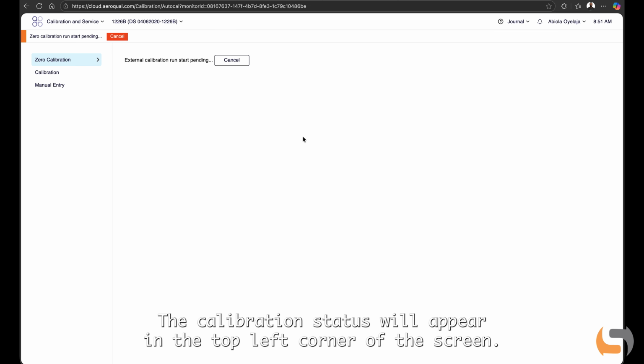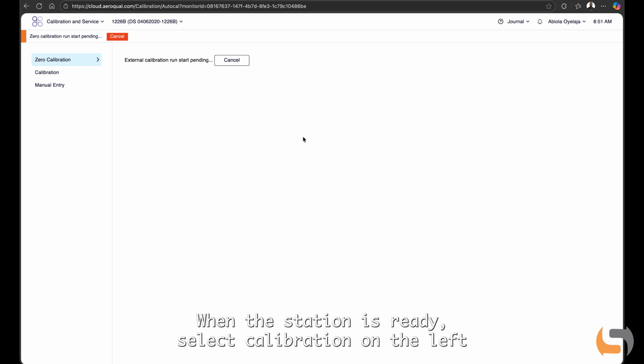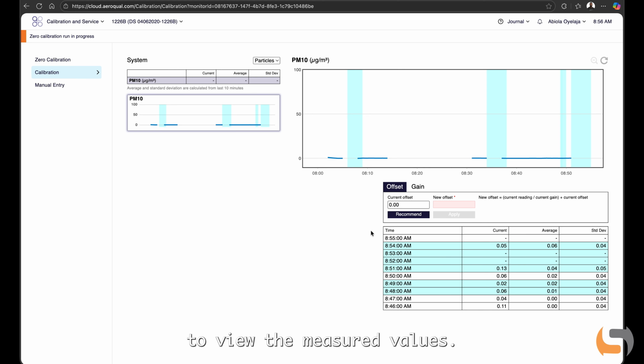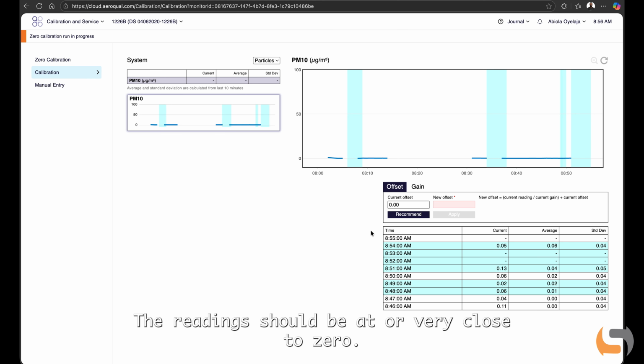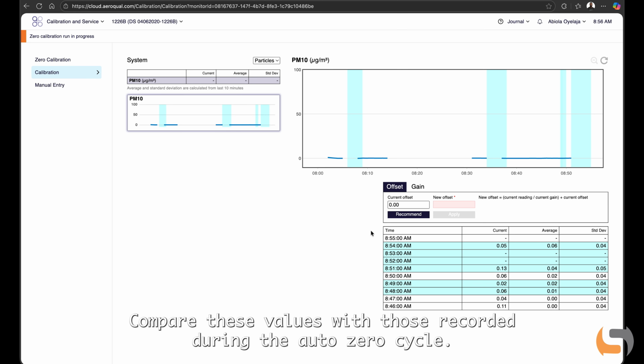The calibration status will appear in the top left corner of the screen. When the station is ready, select Calibration on the left to view the measured values. The reading should be at or very close to zero. Compare these values with those recorded during the auto zero cycle. The results should match or be very similar.